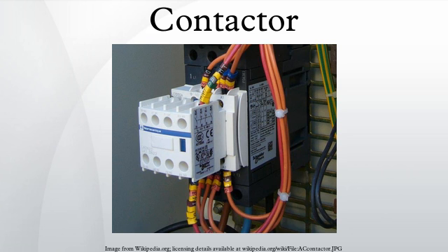A basic contactor will have a coil input. The coil may be energized at the same voltage as a motor the contactor is controlling, or may be separately controlled with a lower coil voltage better suited to control by programmable controllers and lower voltage pilot devices. Certain contactors have series coils connected in the motor circuit. These are used, for example, for automatic acceleration control, where the next stage of resistance is not cut out until the motor current has dropped.